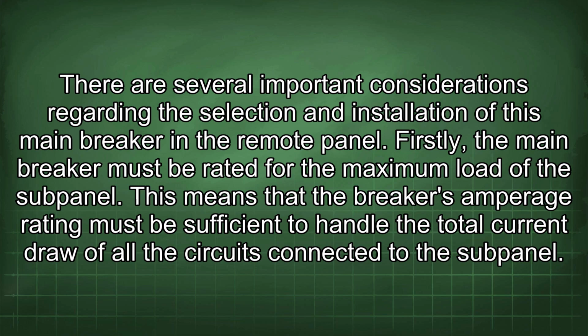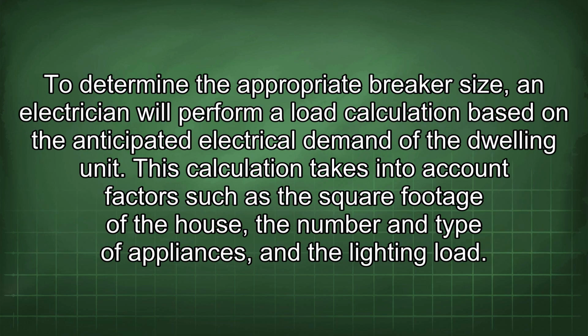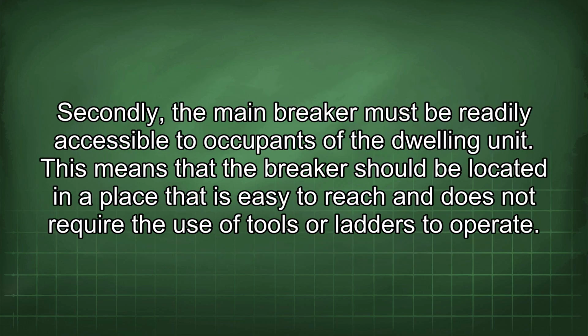There are several important considerations regarding the selection and installation of this main breaker in the remote panel. Firstly, the main breaker must be rated for the maximum load of the subpanel. This means that the breaker's amperage rating must be sufficient to handle the total current draw of all the circuits connected to the subpanel. To determine the appropriate breaker size, an electrician will perform a load calculation based on the anticipated electrical demand of the dwelling unit. This calculation takes into account factors such as the square footage of the house, the number and type of appliances, and the lighting load.